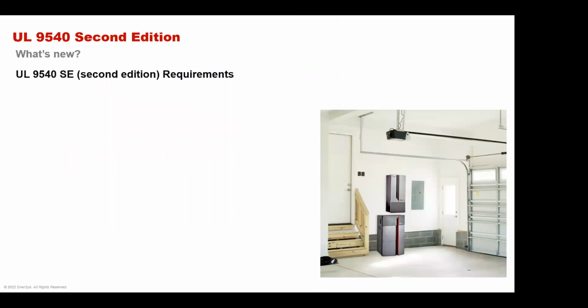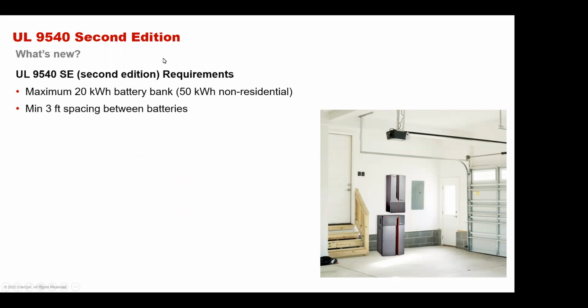And the reason UL 9540A came about is because with UL 9540 second edition, there's now a requirement that says the maximum you can put in a residential home is a 20 kWh battery bank, or 50 kWh non-residential, and there has to be a minimum 3 foot space in between the batteries or battery racks.